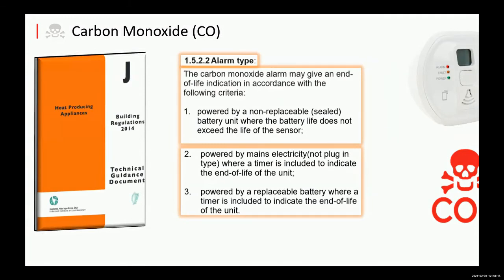The power sources for carbon monoxide alarms. Unlike the smoke detection side of the business, where for new builds, major refurbs and rewires you have to have mains with battery backup, for carbon monoxide you don't. The power sources can be replaceable battery, sealed for life battery, or mains with battery backup. The only unit that's not allowed under the standard is a plug-in unit. That's not allowed because of the location of the devices. If you have to put a carbon monoxide alarm on the ceiling, you wouldn't have a socket in the ceiling to take that, and if you did, it may fall out anyway. So the only unit that's not allowed is the plug-in type.